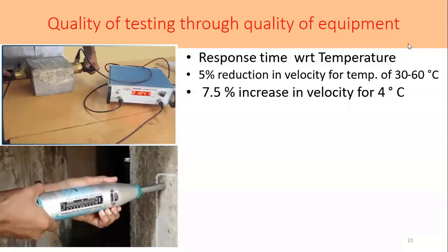Now we are conducting the ultrasonic test even in winter at a temperature of 10 degrees centigrade with the same velocity value. Even if we conduct it in hot summer at 42 degrees centigrade, we consider the same velocity. There is no correction factor applied, neither on the reduction side nor on the increment side. So this is hampering the quality of the testing.